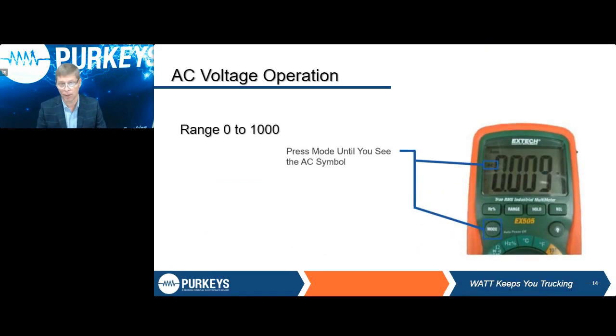This one here, you see we're on AC right now. To toggle it back to DC, you'd have to hit that mode button. The other thing you have to make sure is what your meter's capable of reading. Most of your better meters will go up to 1,000 volts.